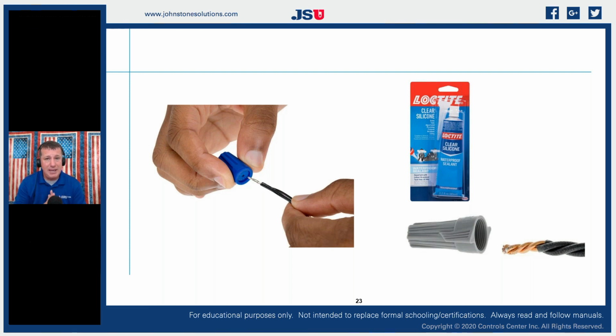Understand that in many applications you can use solid wire, but you need to read the installation manual because some will specify solid or stranded, and some will specify that it is a shielded wire or not. And we'll talk about that a little bit more as we get into some other conductors. Just remember that no matter what we're using, if we are using it for line voltage, we're passing current through that wire. If we're using it for communicating, we're passing communicating signals in low voltage, low current. So the condition of the surface of our conductor plays an entirely different role when we're talking about communicating.